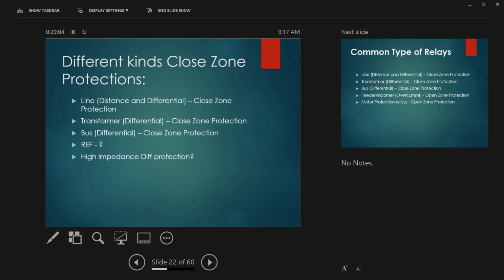What about the REF? Everybody has encountered this. Closed zone or open? REF is restricted earth fault. It's closed. Yes. It's only the transformer, yes, correct. You're looking at the spot of internal fault between the line transformer going back to the neutral. High impedance differential fault, I would say closed zone as well, because you're looking at your summation. You know that Metrosil thing is always instantaneous. You notice that most of these closed zones are always instantaneous trip.